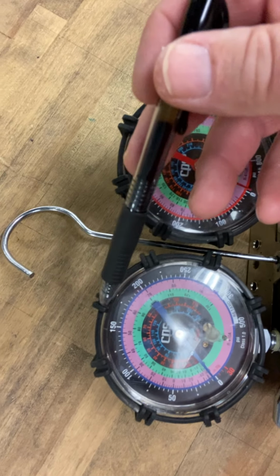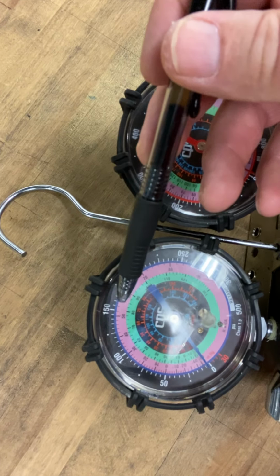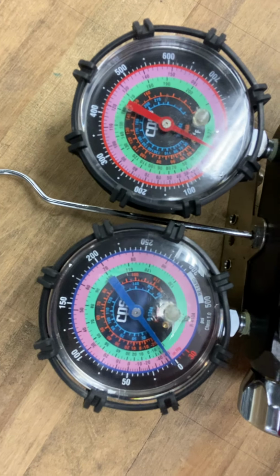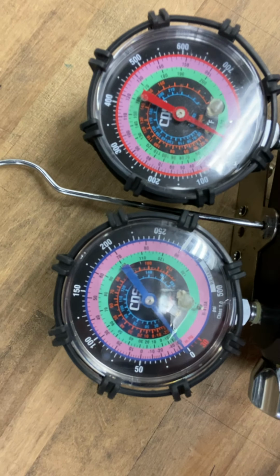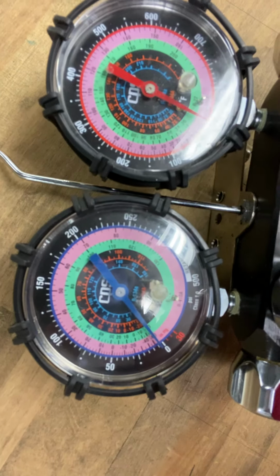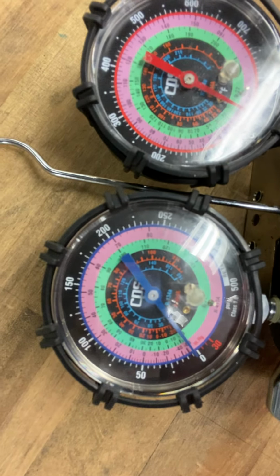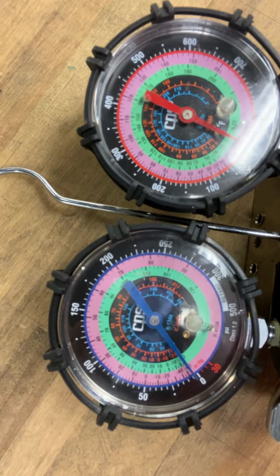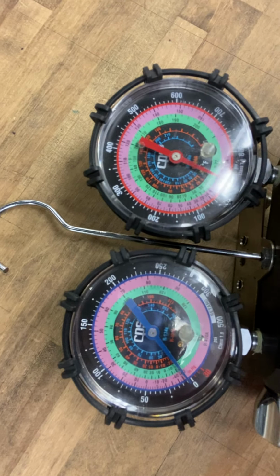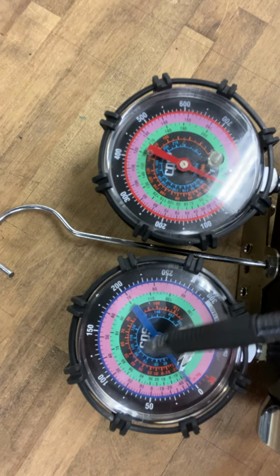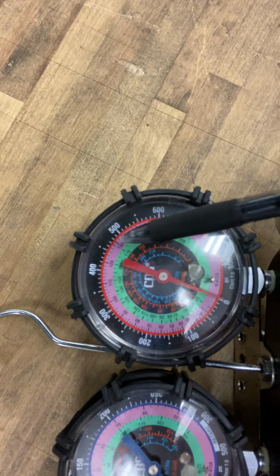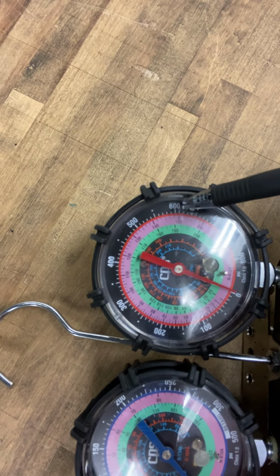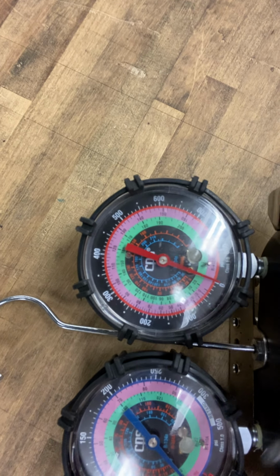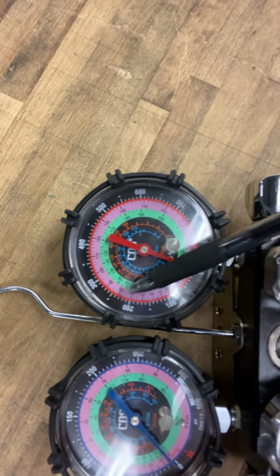So for instance, if I was having a pressure of 150 psi, saturation temperature for 410A would be about 52. Saturation temperature for R22 would be about 79 or 80, somewhere in there. So that's how you read that. Pretty much once you understand how to read one gauge face, they're basically all identical, just different pressure and temperature relationships. So that's that one.